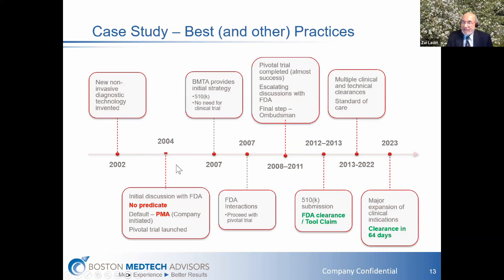And they presented the case to FDA, and they said basically there is no predicate, so we assume the product will be a class 3, as we have seen that's indeed the default. And FDA said, fine, it's your decision. You want to pursue a PMA for that product, go ahead. And as you currently are aware, any product that goes through class 3 requires clinical data, and typically that is done in the context of a pivotal trial.